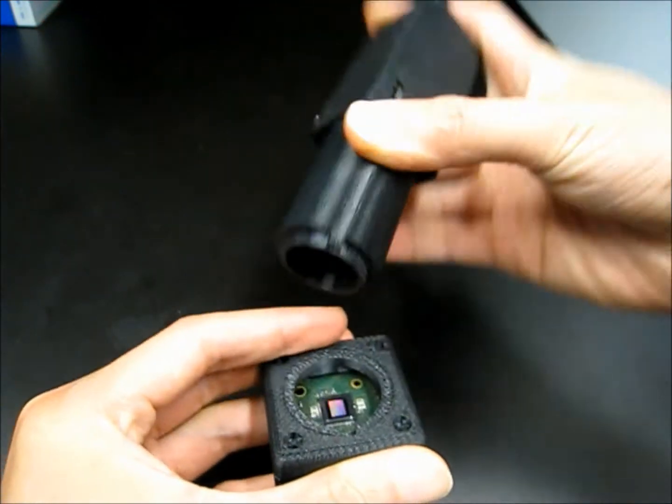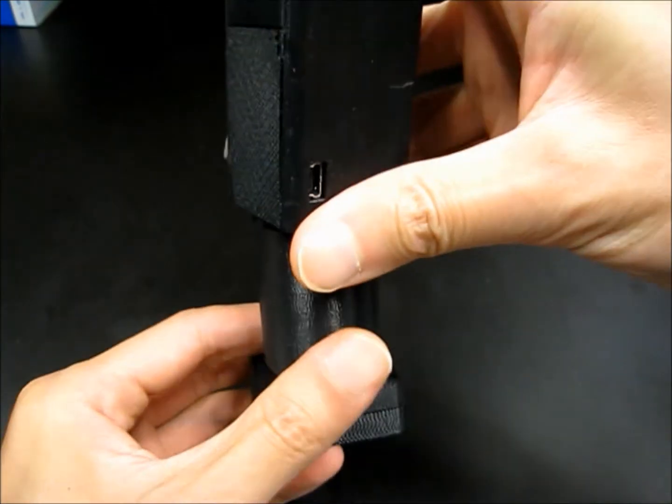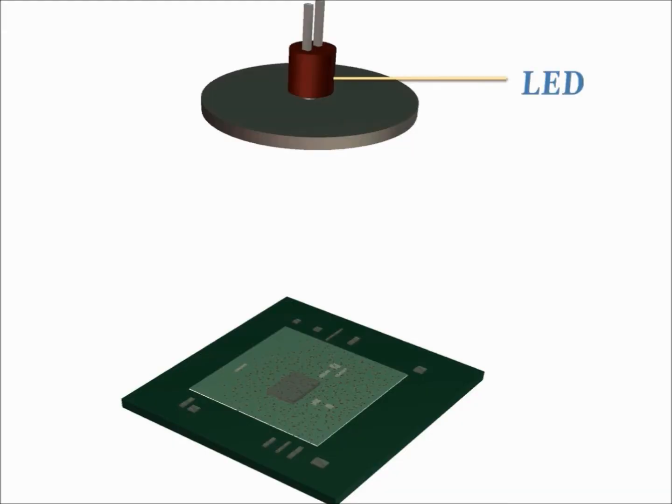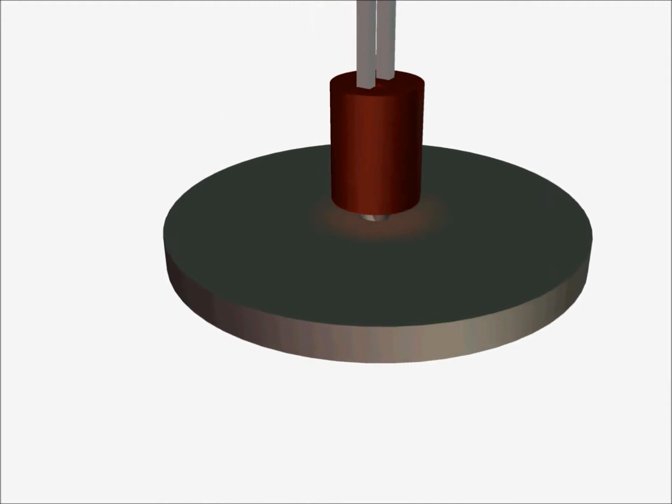Our microscope does not have lenses, so we cannot focus the image of the object on our camera sensor. Instead, we use a technique called holography, which lets us record a defocused image of the object called the hologram, and then digitally process it to get the focused image of the object, similar to a traditional microscope image.